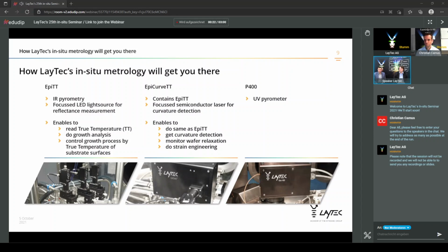Not all layers are suitable for using an IR pyrometer. Therefore, LayTec also has a UV pyrometer in the portfolio. This is the P400 or Pyro 400. This sensor enables you to measure the surface temperature on IR transparent layers, for example, gallium nitride. At UV wavelengths, gallium nitride at growth temperature is opaque, so in that range you are able to measure again the real true surface temperature. And not only to measure it somehow, it makes the measurement free from Fabry-Perot oscillations. This is especially necessary on sapphire substrates or PSS, where gallium nitride especially is grown for LED or laser application.